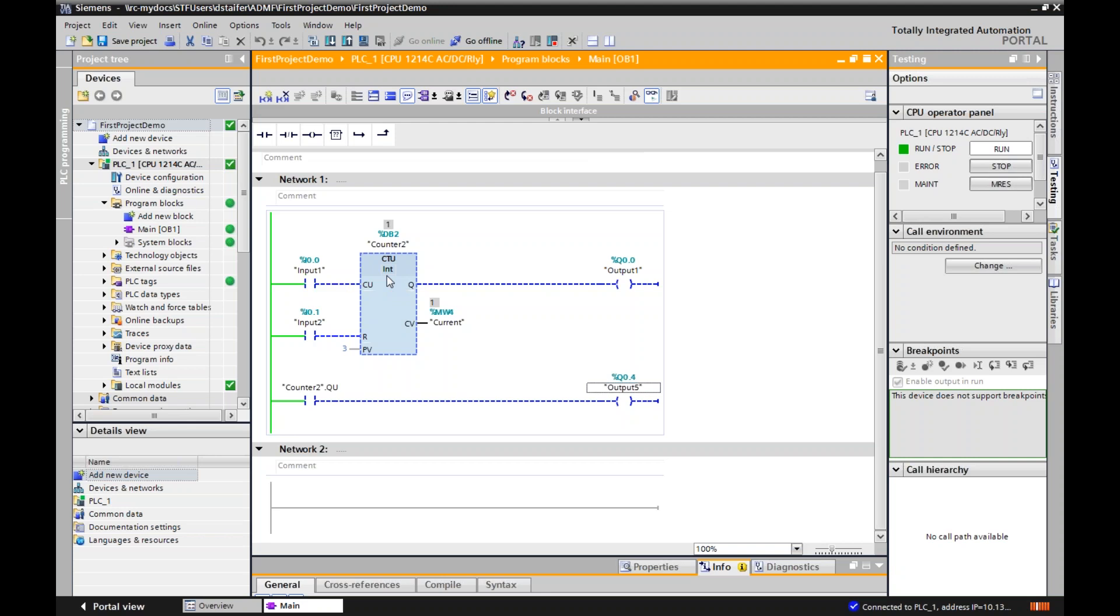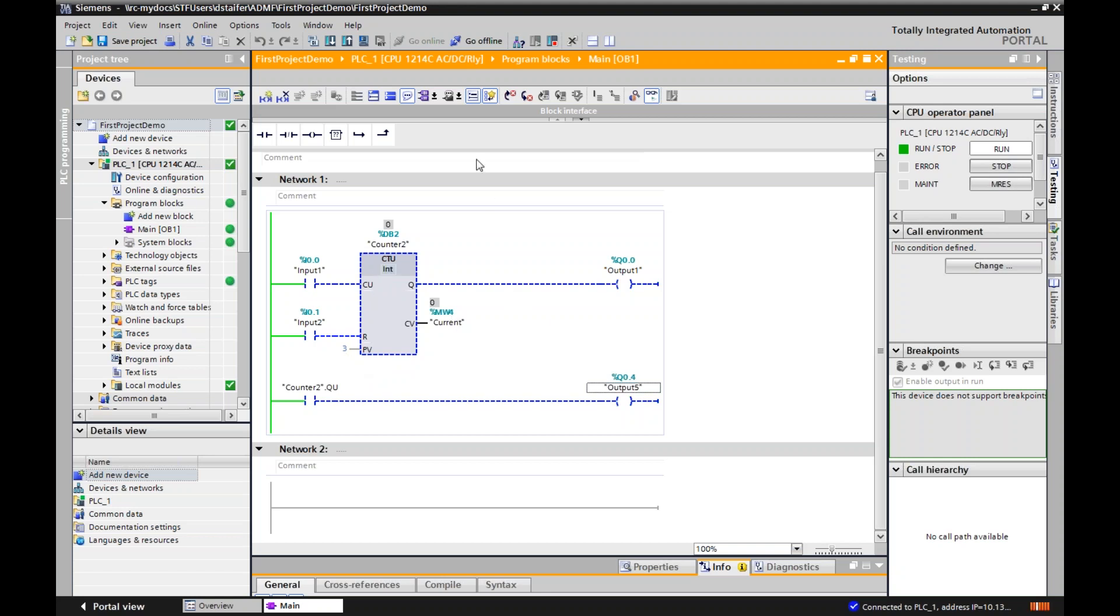So now I can keep going. And if I hit reset, now reset. Unlike a timer, or just like a timer, if I do a reset before it hits its preset condition, it's going to reset. Unlike a timer though, if my initial conditions go false, it won't lose count in any way. Because that's the purpose of a counter, to keep count, and you can see it go up and go down. Hooray, it's wonderful. So I'm going to reset it so I turn my lights off. And now I've got a zero in the current value, three in the preset, and I'm going to go offline.